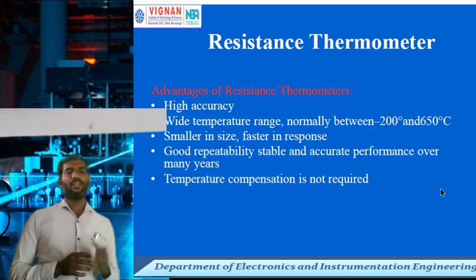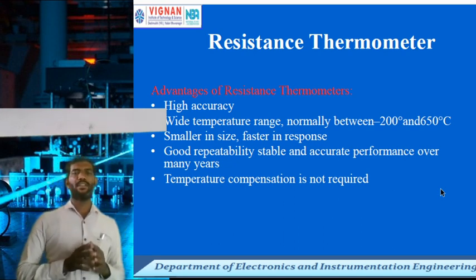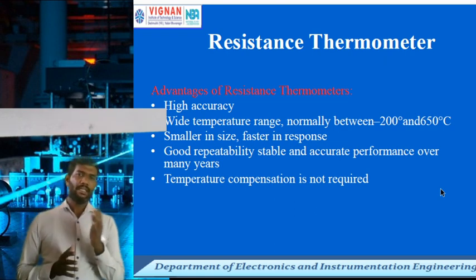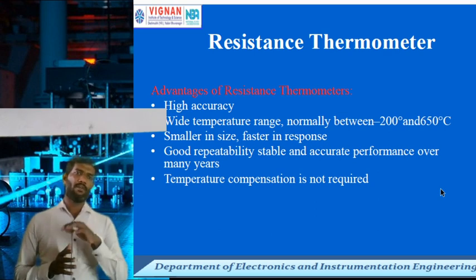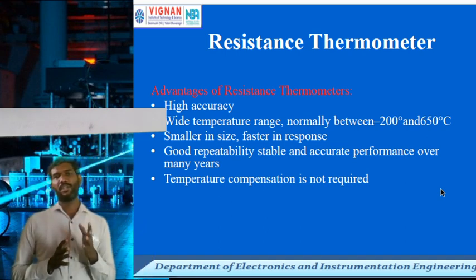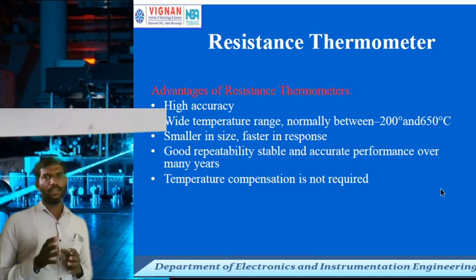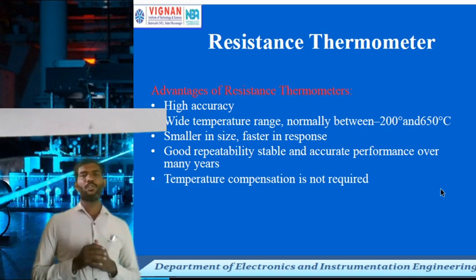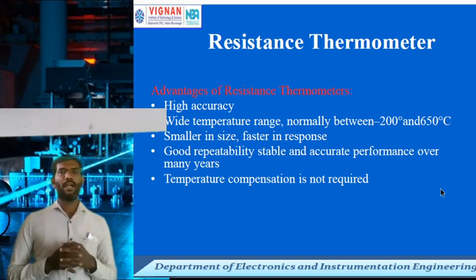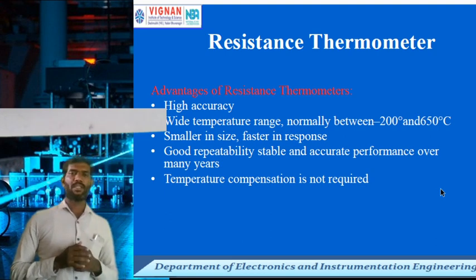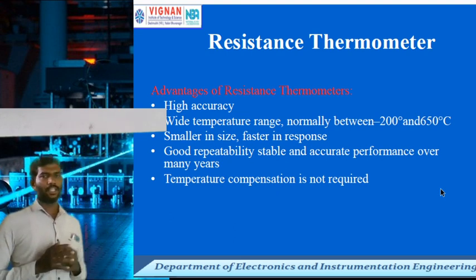Now let us see the advantages and disadvantages of thermocouple, thermistor, and RTD. We are going to prefer another type of instrument used in blast furnace temperature measurement — the pyrometer. Among all temperature measuring instruments, RTD is also one of the important instruments, having different advantages: high accuracy, used in a wide range of temperatures from minus 200 to 650 degrees centigrade, small in size, fast response, and good repeatability.